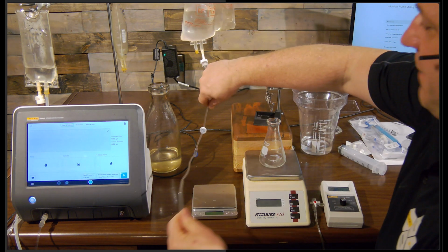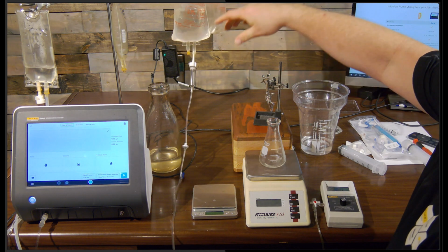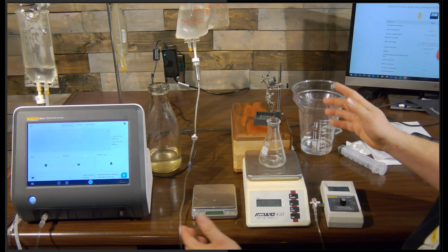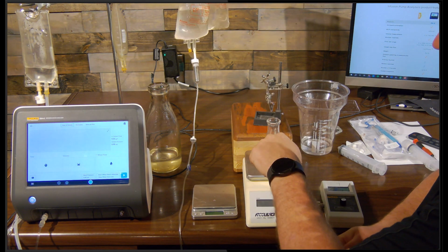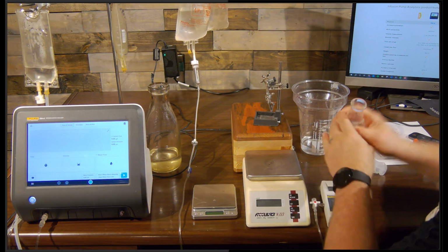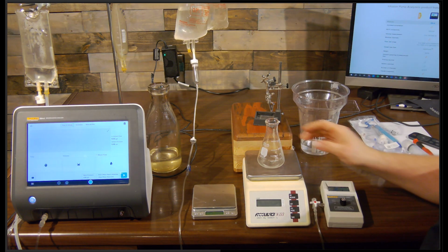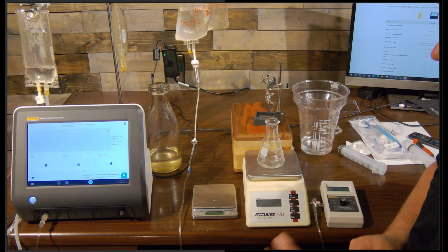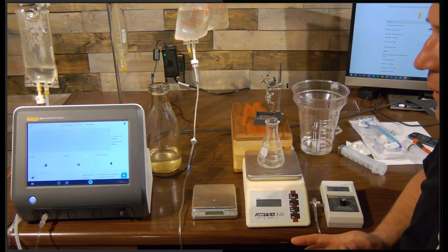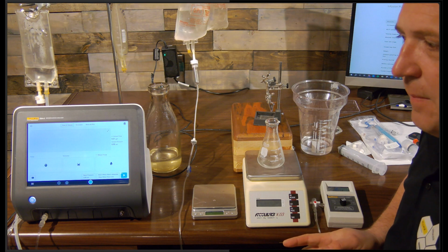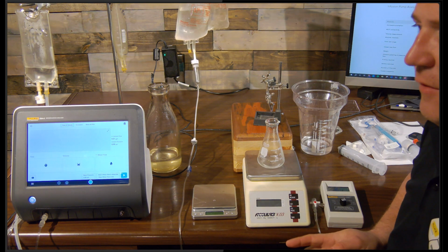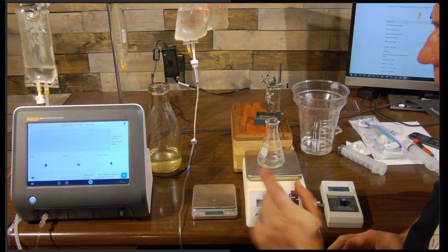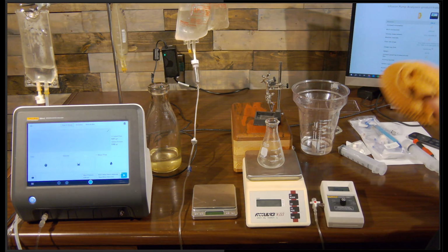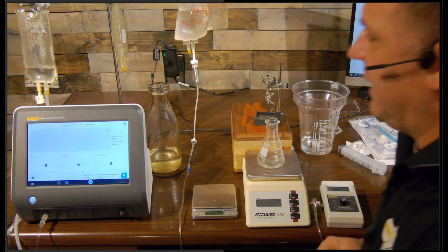So when you add up that possibility of error, not using a normal test set, splashing water all over, having towels underneath your scale, that adds another variable. Did you catch the peak? That adds another variable. Did you dump everything out of your beaker? That adds another variable. Did you remember to push tare at the right time? That adds another variable. You end up with all these potential failure points. And that could be a real challenge for infusion pump testing, because now all of a sudden when you string those together, your tolerance is really wide. So that's why I like to show the IDA-6. And then the IDA-6 is a little bit of a different story.